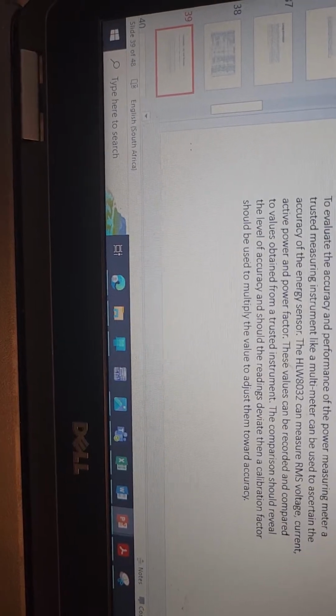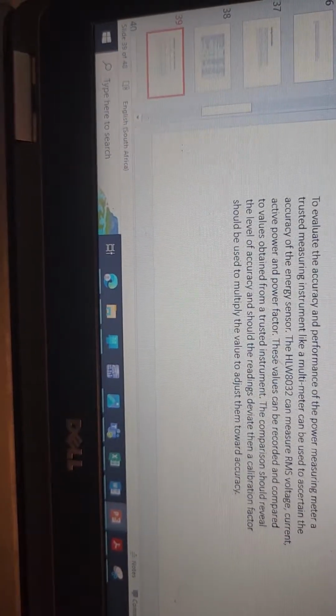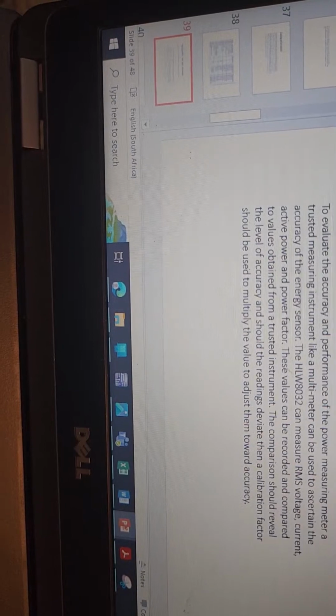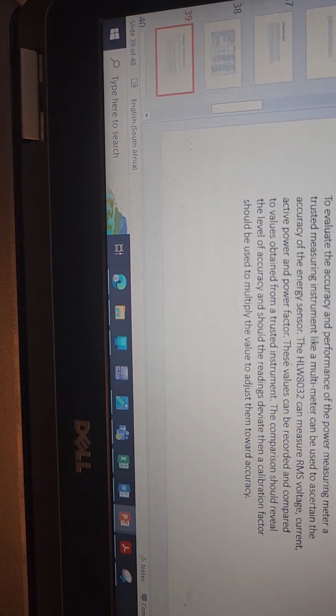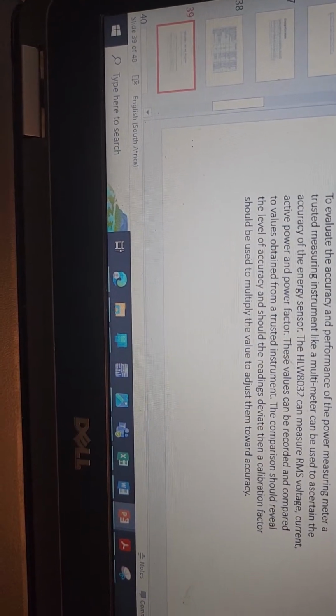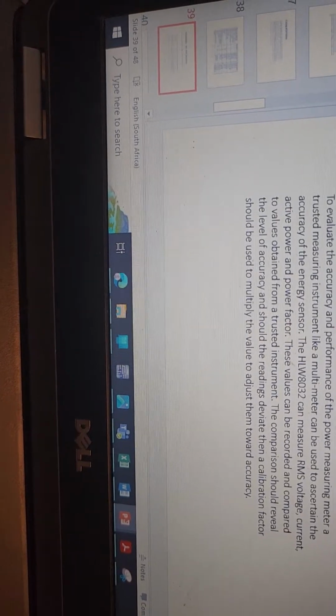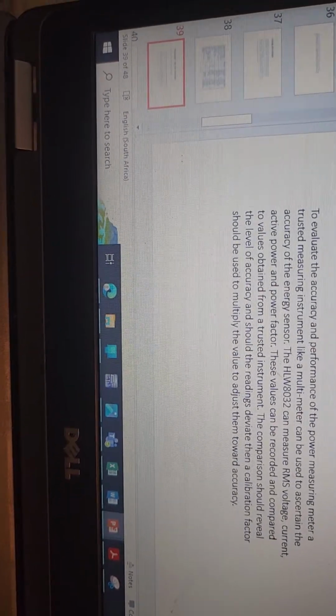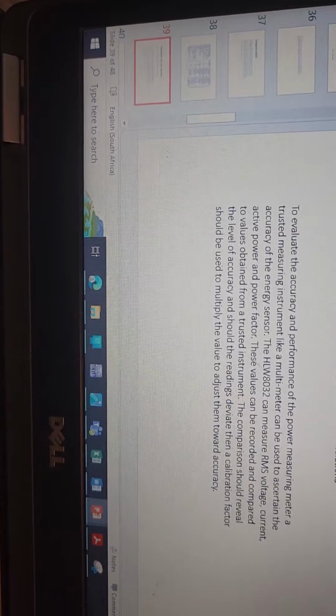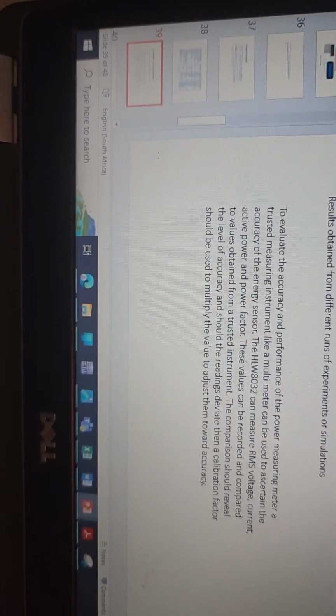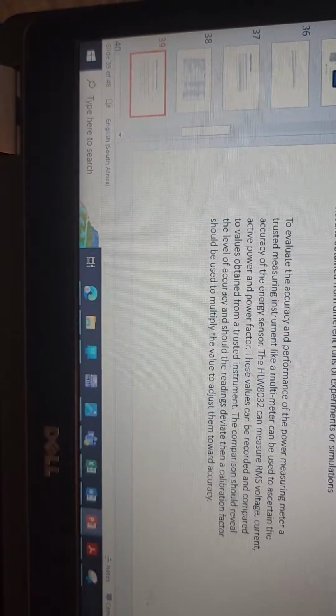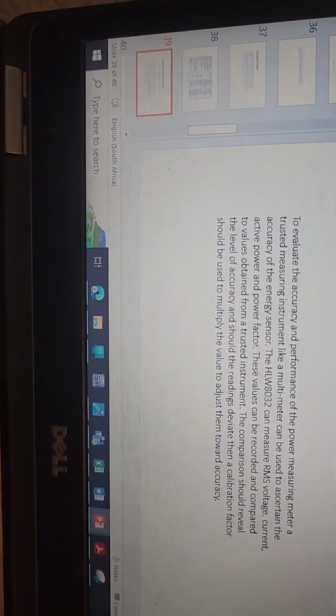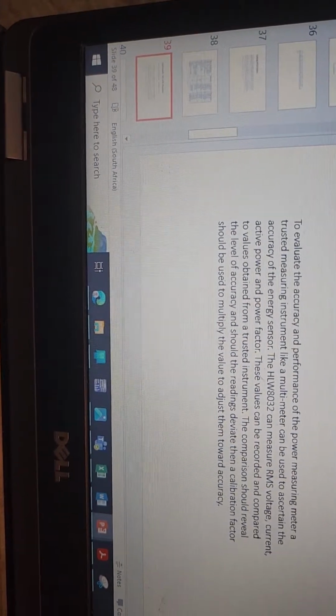The HLW8032 can measure RMS voltage, current, active power, and power factor. Those values can be recorded and compared to the value obtained from the trusted instrument. This comparison should reveal the level of accuracy, and should the reading deviate, a calibration factor should be used to multiply the value to adjust it towards accuracy.